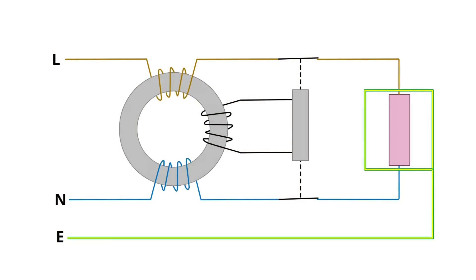Now, we've got a diagram here of a traditional RCD, what's referred to as an AC type RCD, which is the basic RCD that we've mostly been installing for years and years. Inside the RCD, the line conductor wraps around this toroidal, or ring-shaped, piece of soft iron. It then goes off and feeds the load. The neutral from the load then returns and wraps around the other side of the toroidal core and returns to the source of supply.